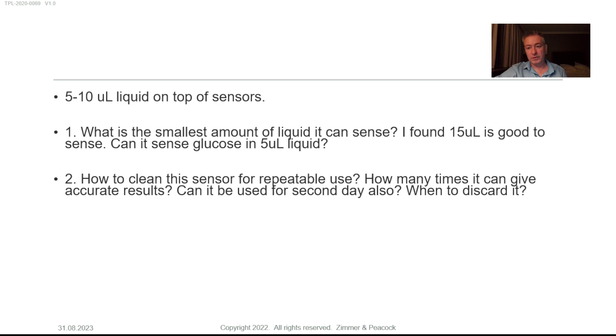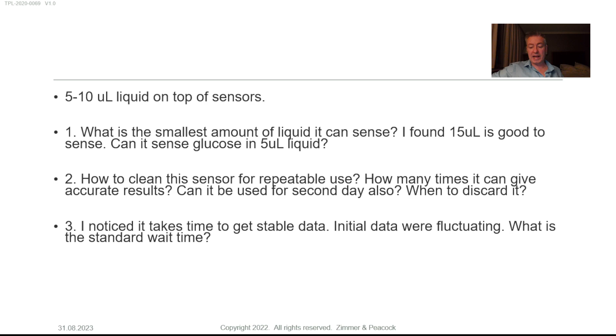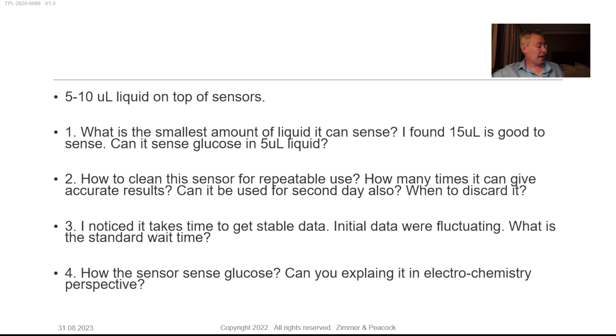It takes a while to get a stable signal, or he says data, but stable signal. Yeah, it does take about, for us, 100 seconds sometimes to get a stable signal. Sometimes we allow it to stabilize for 500 seconds. I mean, the sensors that you have are intended for CGM, continuous glucose monitoring. So these kind of settling times are really sort of acceptable. If you put an Abbott Libre Freestyle 2 or 3 on your arm, which is a leading CGM on the market, then those will take an hour to settle before they will actually start giving you signals.